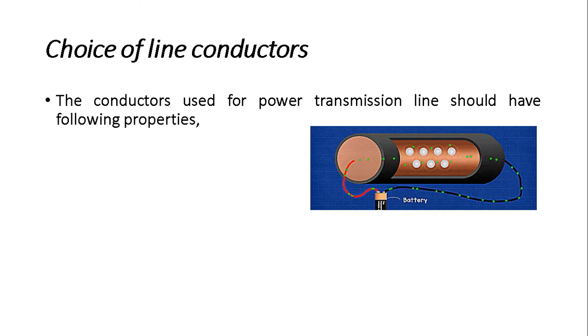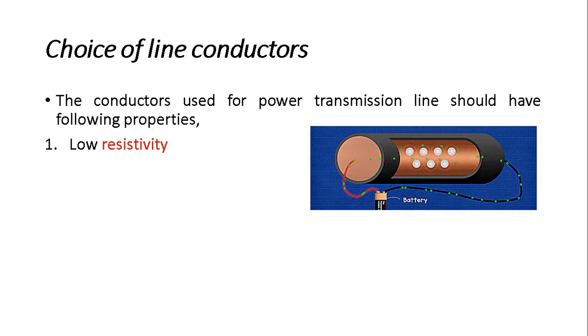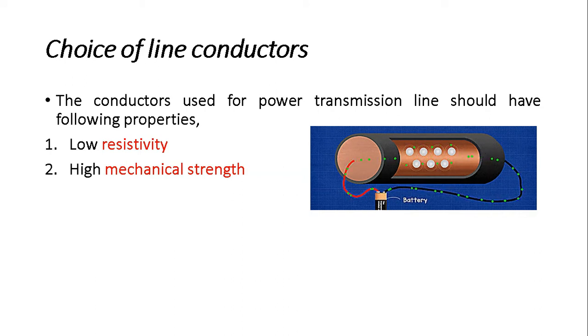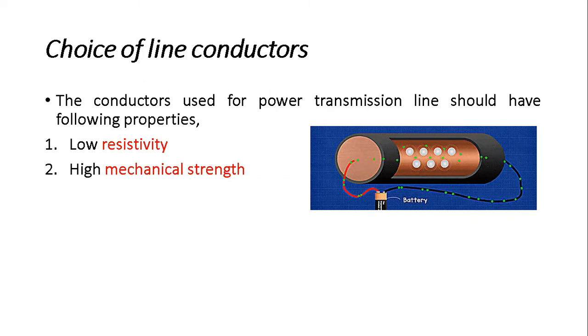The conductor used for transmission as well as distribution purposes should have certain properties. The first property is low resistivity, or high conductivity, in order to carry more power or more current. The second property is high mechanical strength, or tensile strength, to withstand heavy mechanical load — because in certain cases conductors must be ready for ice, stone, and wind conditions. Mechanical strength should be as high as possible.